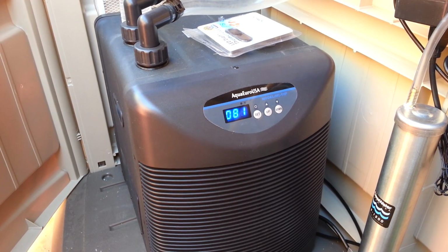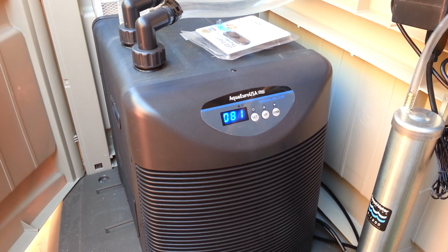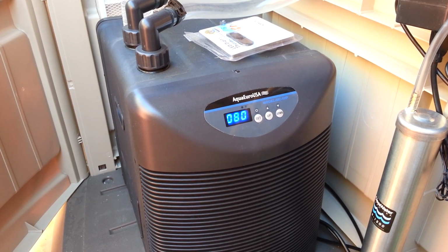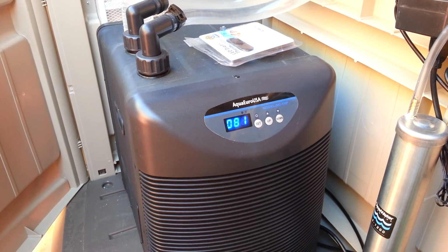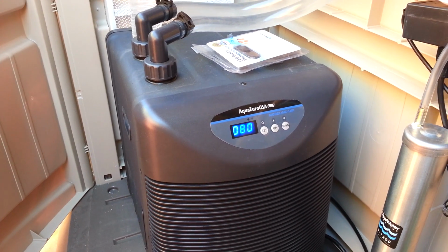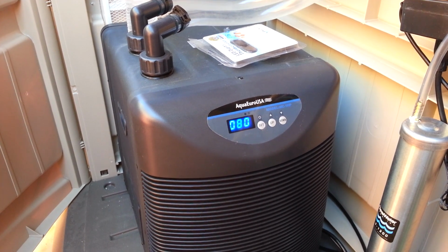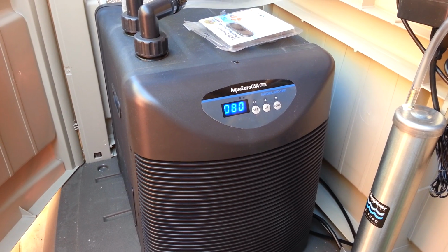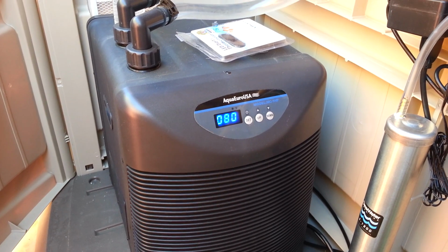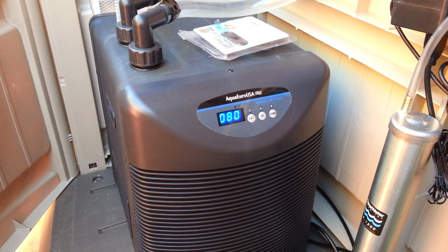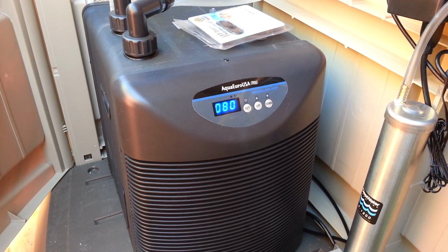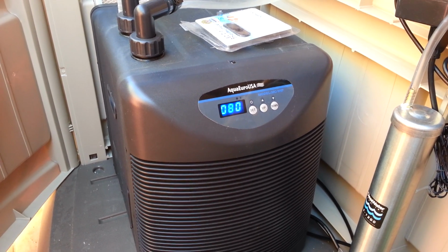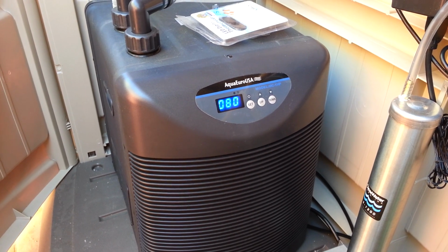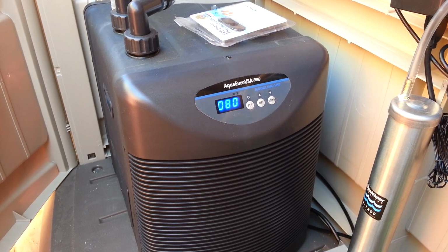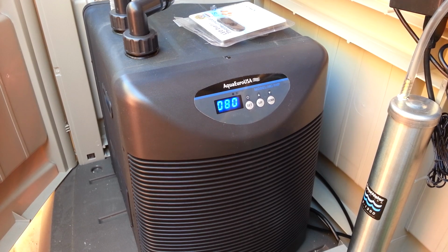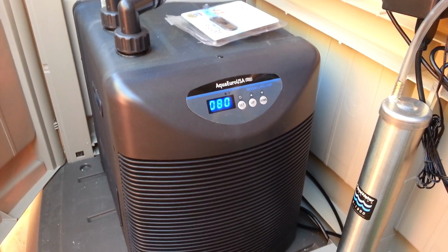And usually within about a minute or so, yeah, there you go, it starts to go down again. The temperature is now lowering with the chiller off. So I don't know if something's wired backwards or if the whole thing is just malfunctioning in some way, but I've never seen a chiller that actually goes up in temperature when it's on and goes down in temperature when it's off. But obviously there's something wrong.